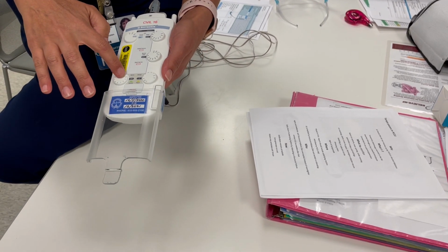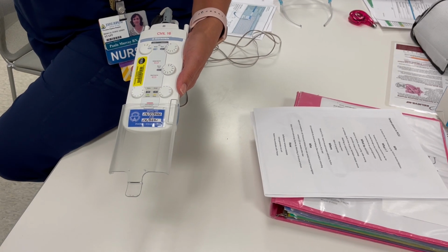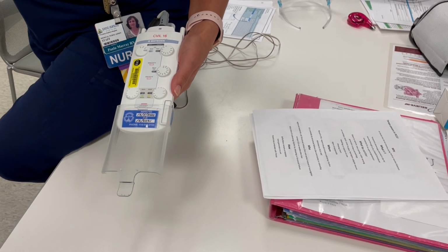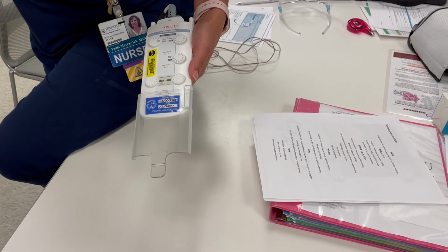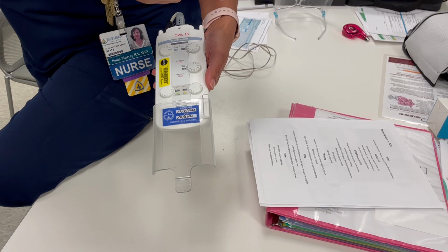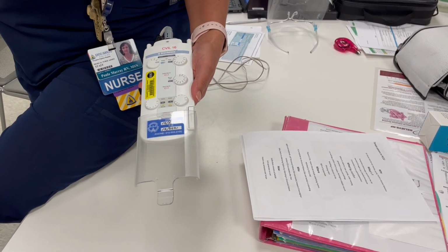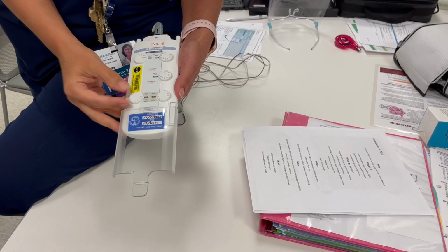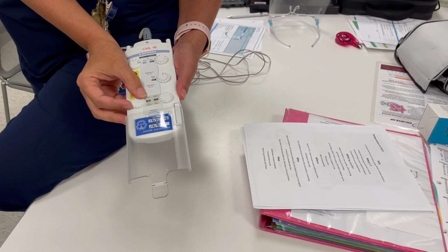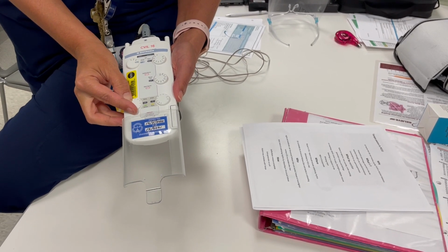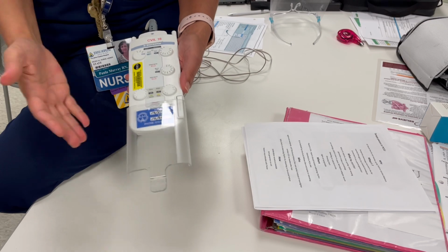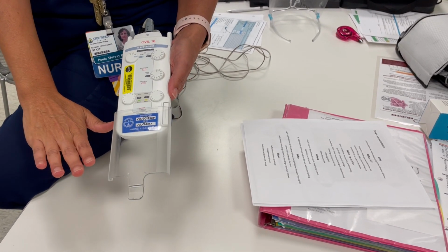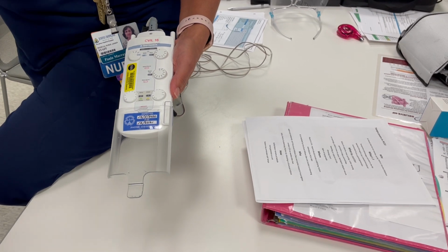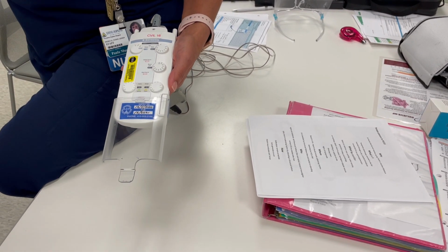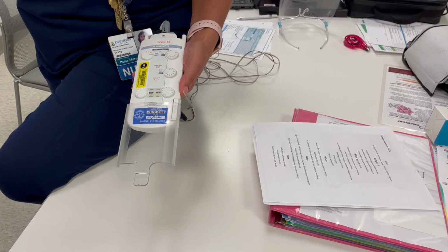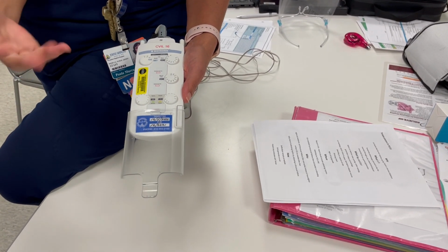Think of 20 as 20 feet in the air. If I have 20 feet between me and Noelle, I can't see Noelle. If I can't see her, then I can't withhold my pacer spike. I'm just going to do what pacemakers do, and I'm going to pace. So the higher the number, the less sensitive it is. You are most likely going to have it around 2, maybe 2.5, somewhere in there. You want it down low so that the pacemaker can see the intrinsic rhythm, and if it sees it at the right time, it will withhold pacing.